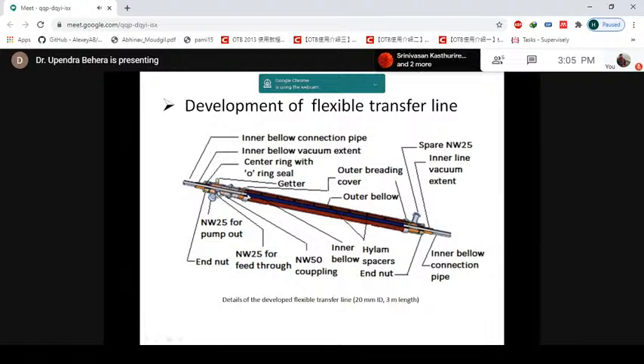They need these for their tokamak applications, for transferring a large quantity of helium, and it is a flexible one for better maneuverability. Initially they have given some data that in the range of 10 to 15 liters per minute of liquid helium should flow through this flexible transfer line, and we have done the calculation based on the design parameters given, and also I'll show you some more.